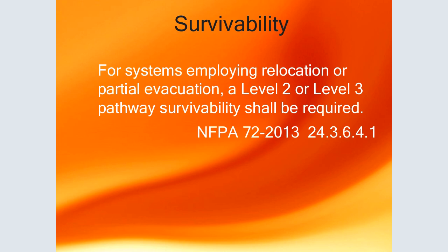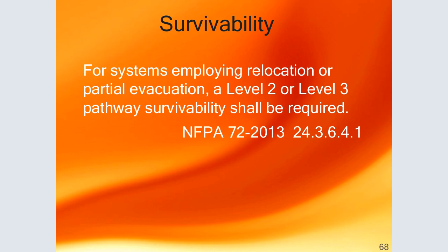For the system employing a relocation or partial evacuation, a level 2 or level 3 pathway survivability shall be required.